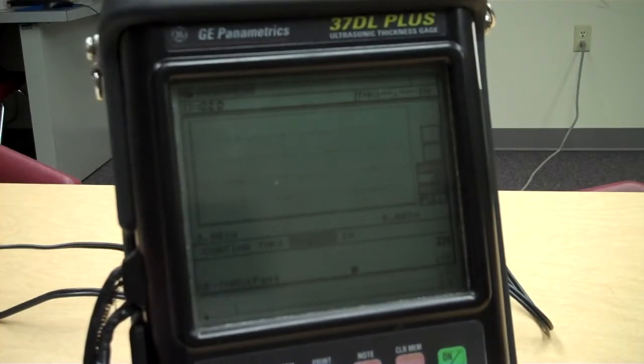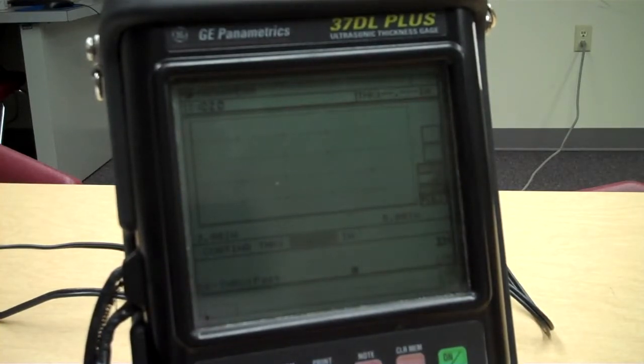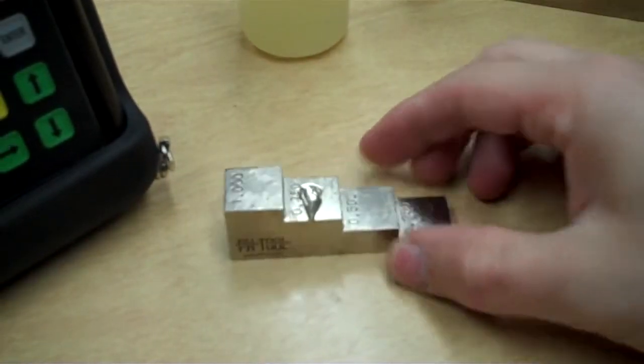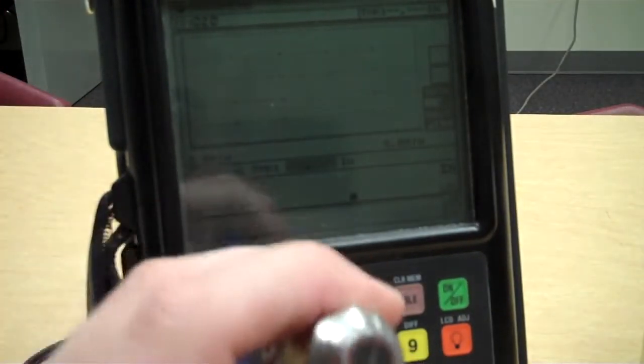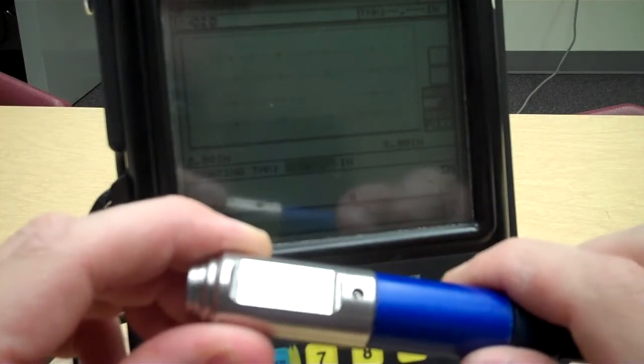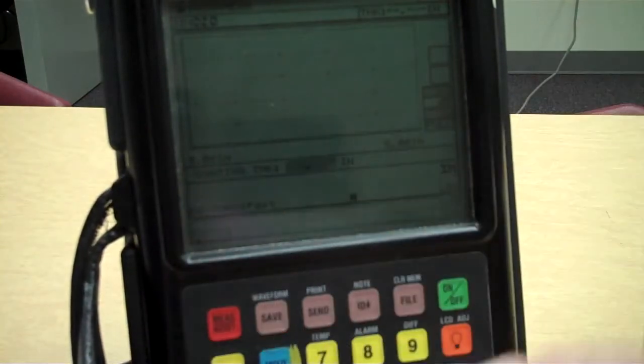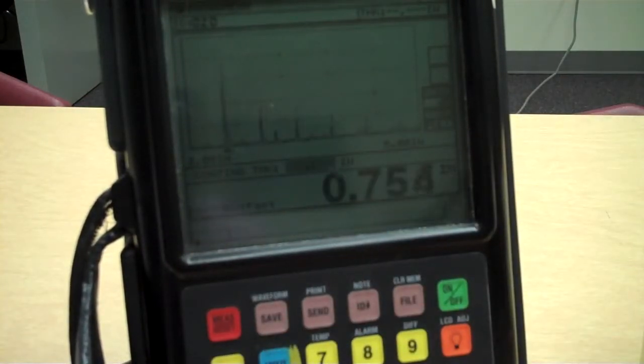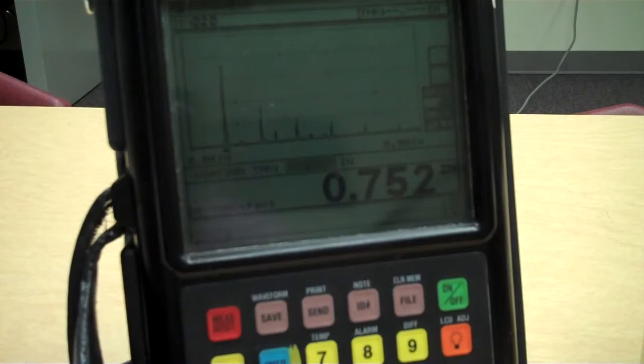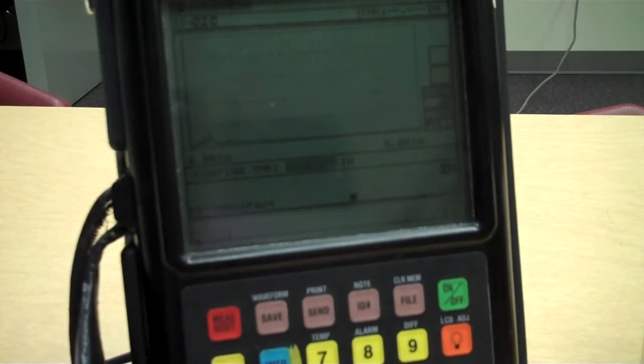Now let's just put a little couplant down on a step wedge here. Show you the step wedge we're working with. Just a little step wedge. Okay. Here's my dual element transducer that goes along with this thickness gauge. Okay. This is a Panametrics D7906. You probably can't see that because of the glare. D7906 5 megahertz transducer. So if I just put this 5 megahertz transducer down on here, it looks already like, whoops, we were pretty close to a calibration before.